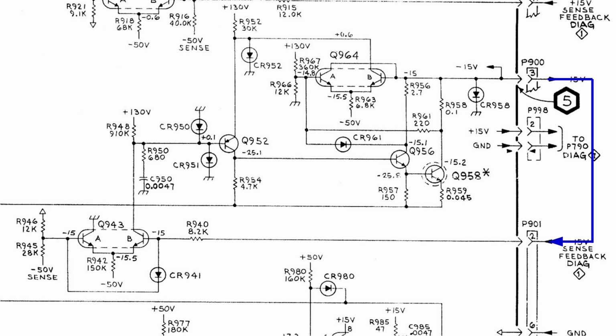To begin with, let's recognize there's a feedback loop in play. Whatever this circuit puts out goes to the rest of the instrument, and at a distant point there's a separate wire coming back with the voltage at the remote point. The reason is that the wire carrying the power has non-zero resistance and carries the full current of the supply, so it has a small voltage drop. The sense wire carries nearly no current, so it can accurately sense the 15 volts at the load, and the feedback loop compensates for the wiring resistance.